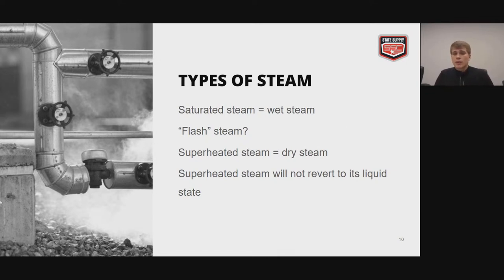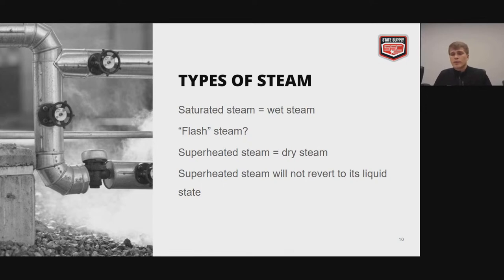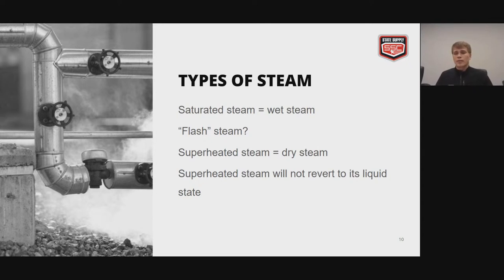Flash steam happens when there's a pressure drop. Under pressure, condensate can exist at higher temperatures than 212 degrees. So if you have condensate at 230 degrees at 10 psi and you bring it to atmosphere, a portion of that water would flash off into steam because water can only exist at atmospheric pressure at 212 degrees. Superheated steam is known as a dry steam — the steam is actually above the boiling point of water, having been heated after conversion into steam. This will not allow water droplets to form, and it will not revert to liquid state.